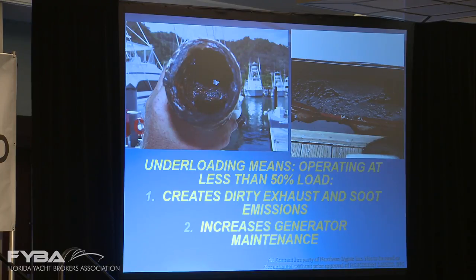We have a problem that we didn't used to have, and that is that, well, actually several problems. The biggest one is that at relatively low exhaust temperatures, which are caused by low generator loads, carbon forms in the exhaust system, and it can even plug up the exhaust system. That carbon also goes to other places in the exhaust system where it's collected, particularly gas-water separators, and in the case of big yachts, sometimes that carbon is actually swept out, filtered out with the water, and it appears below the water line, and then it's pretty nasty looking. And in small quantities, it forms a sheen on the water. In large quantities, of course, it looks like a big black oily mess. So this is a big deal.